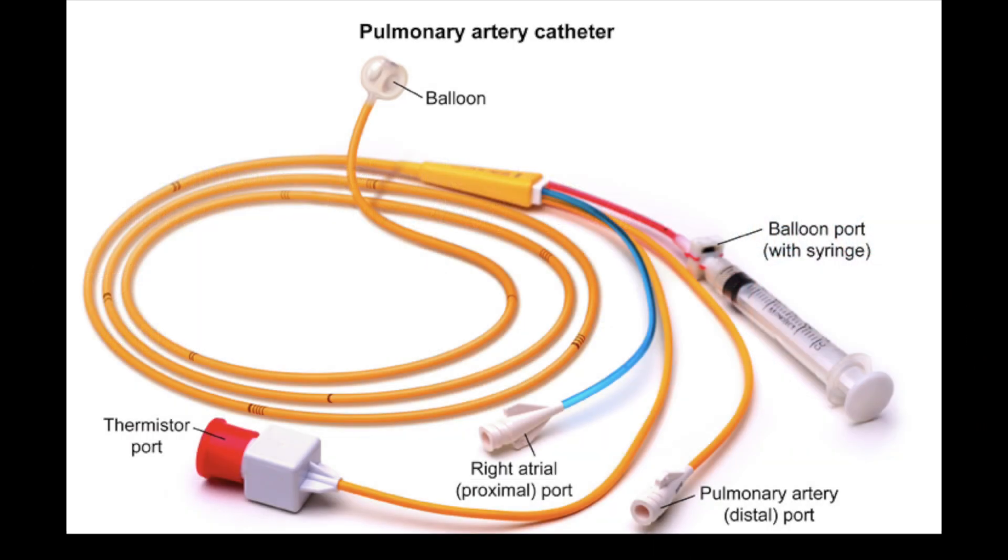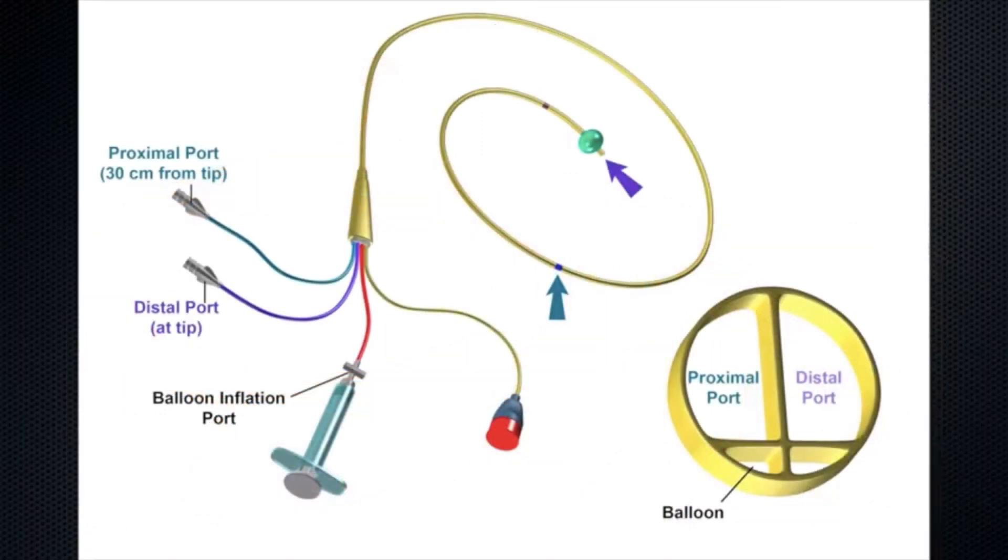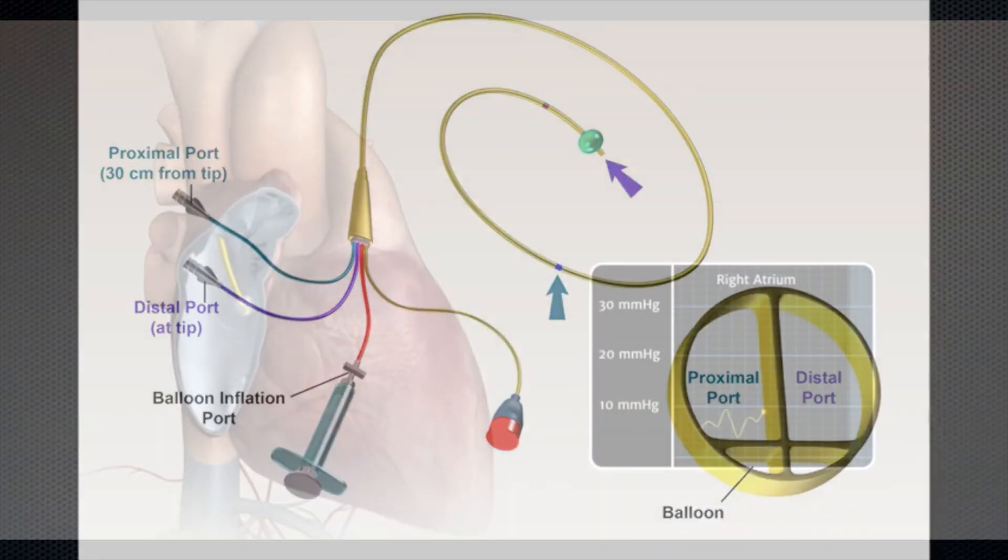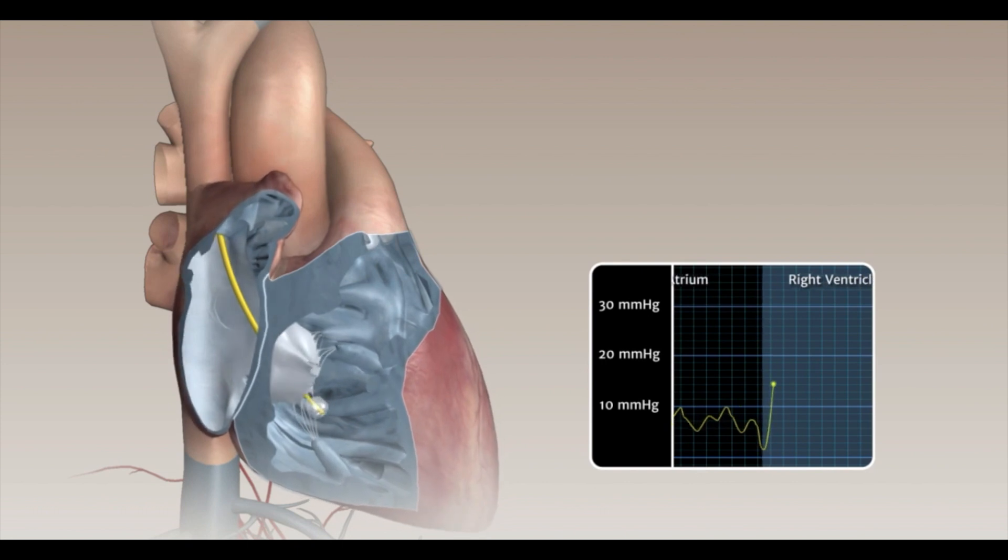Continuous cardiac output is obtained by the thermodilution method, which is a pulmonary catheter that contains a thermal filament 10 cm in length, in addition to the thermistor located near the distal tip. The thermal filament is in proper position when it is located in the right ventricle. The filament emits 7.5 watts of thermal energy into the surrounding blood. The thermistor detects the changes in blood temperature, and the continuous cardiac output computer plots thermal curves for calculation of cardiac output.